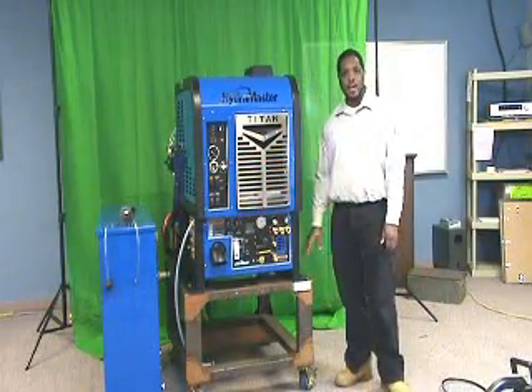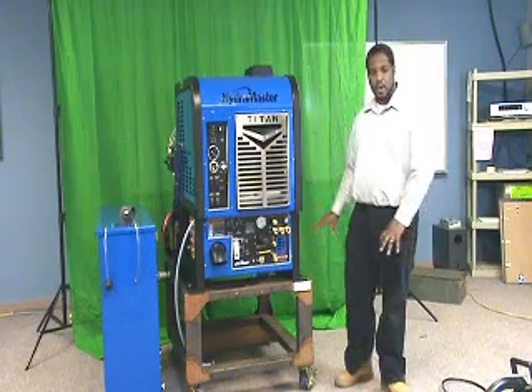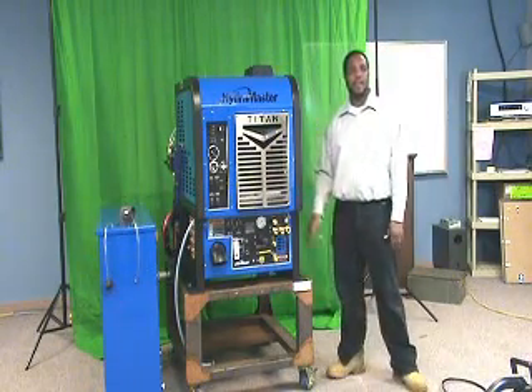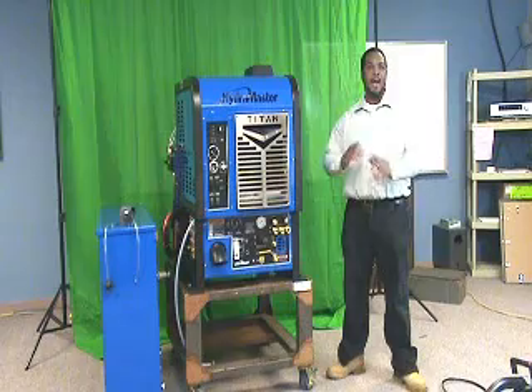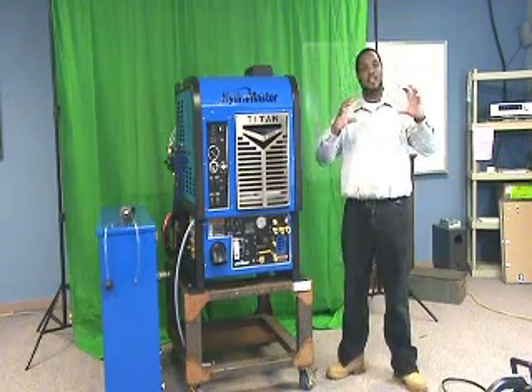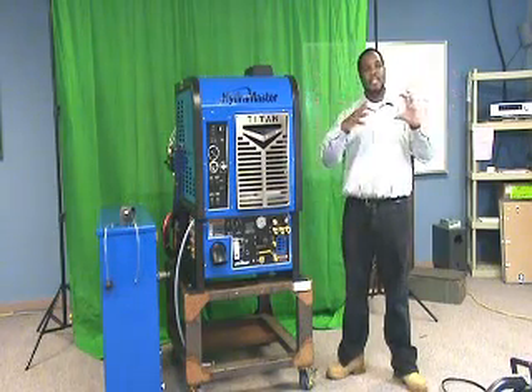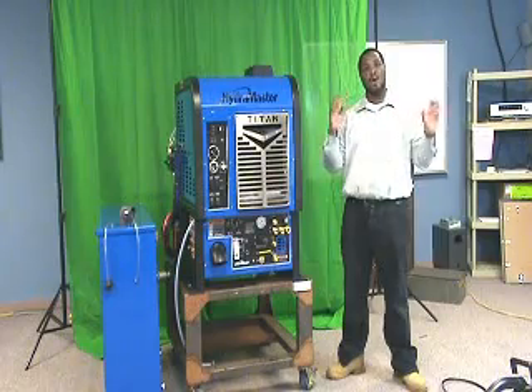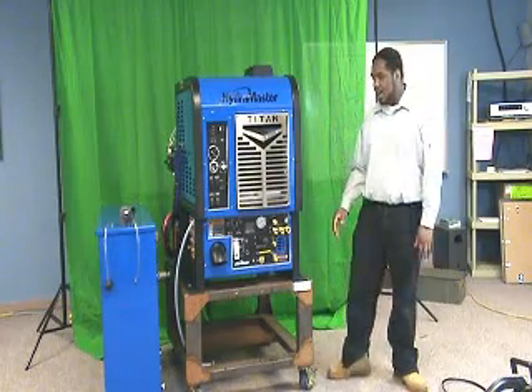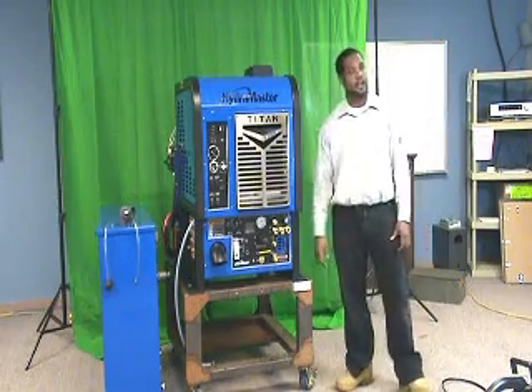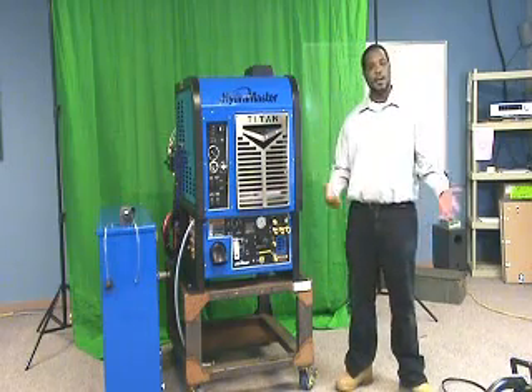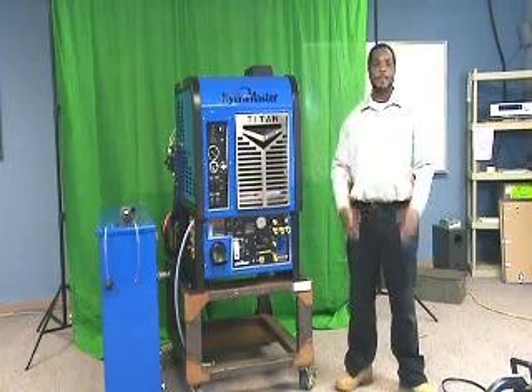Calcium deposits inside the truck mount, otherwise known as hard water deposits, can cause a significant reduction in heat performance by blocking the internal surfaces of the heat exchanger, preventing heat transfer into the solution or the water that's going through. So we highly recommend you descale the machine on a regular basis, which will vary depending on how hard the water is that you're using.